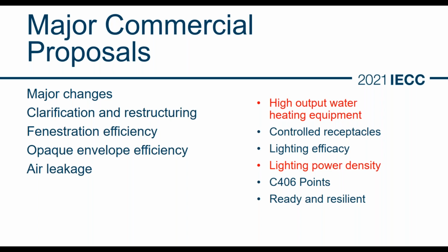Some of the changes that actually made it through, for example, that we won't be hearing in Las Vegas. One is new lighting power density values. ASHRAE came up with new lighting power density for both the whole building numbers and the space by space numbers. In some cases, there is at least a 10% increase in efficiency, which correlates to a 10% decrease in the lighting power density that's going to be allowed to be installed. So there's some pretty significant energy savings in those new tables. They passed. There were no public comments submitted, so those will go to what we call the consent agenda to be voted in with a whole number of proposals that weren't challenged through public comment.